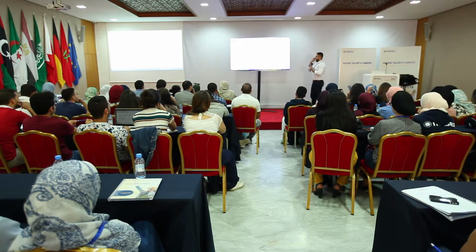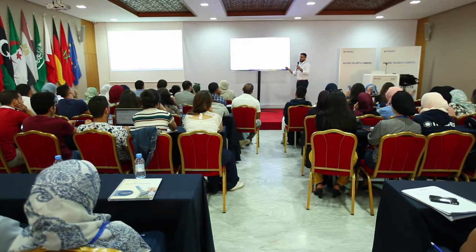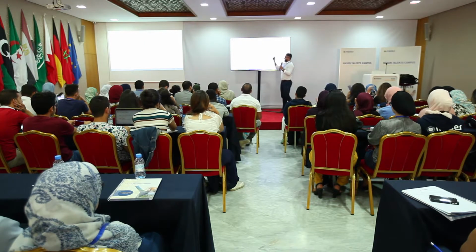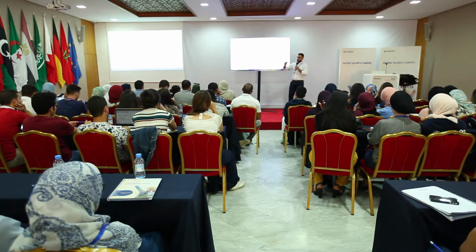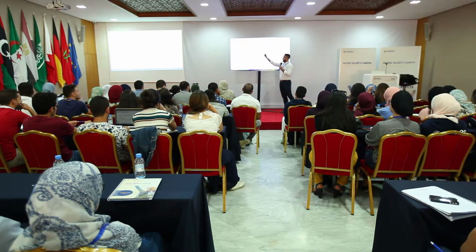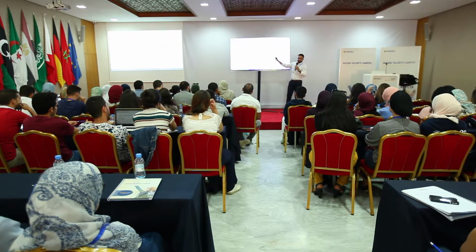So in designing the systems, you need to have an annual simulation, which means you need to use hourly data for a typical year. Because only one point of that was used for sizing, but in reality, the performance, which is how the plant really acts for a given size, depends on the weather conditions, because this is solar energy. And solar radiation and position and everything is varying at all times. So the output of the plant will vary at all times.